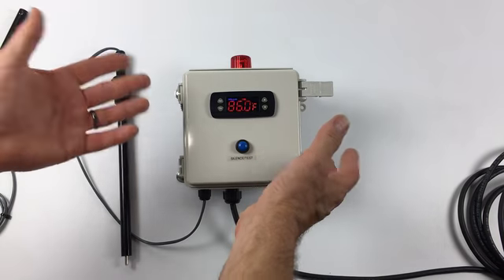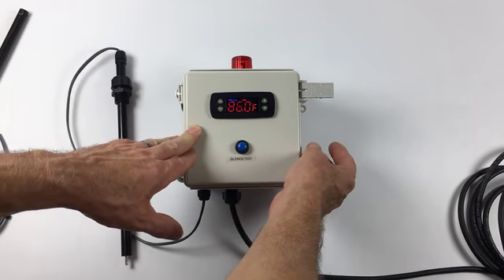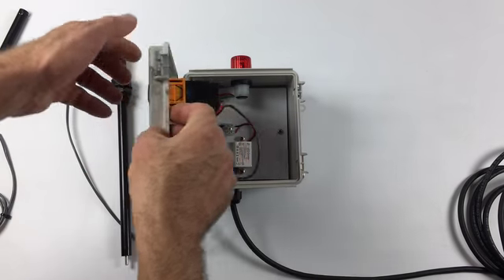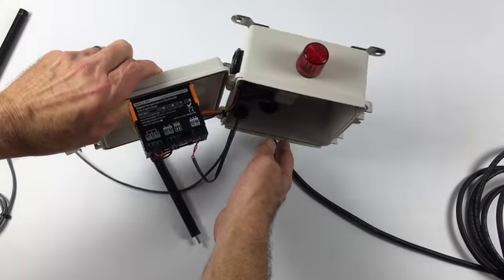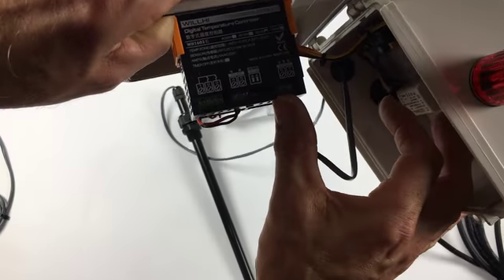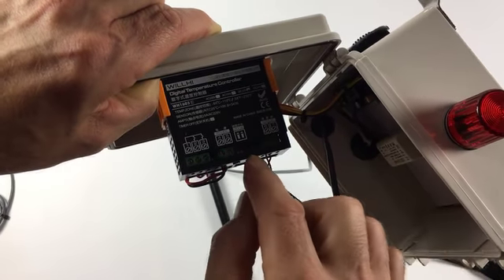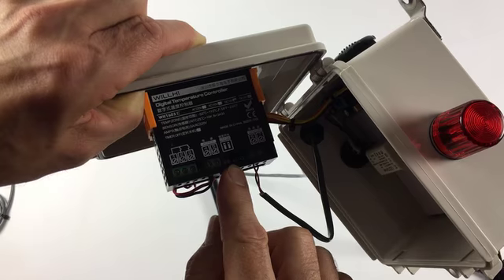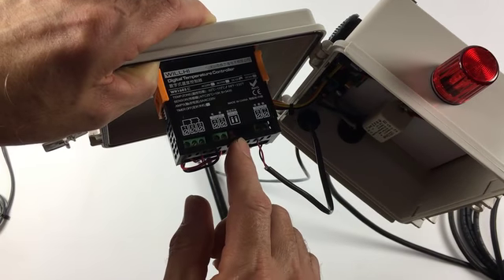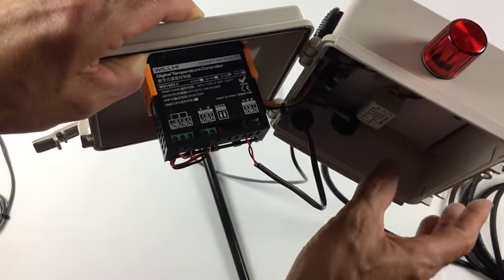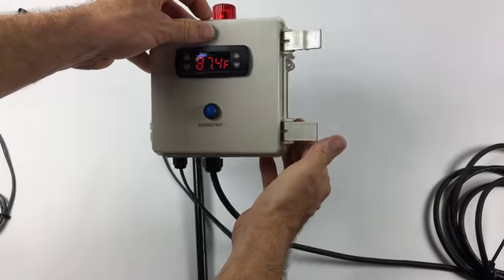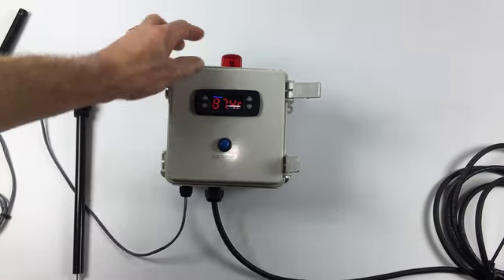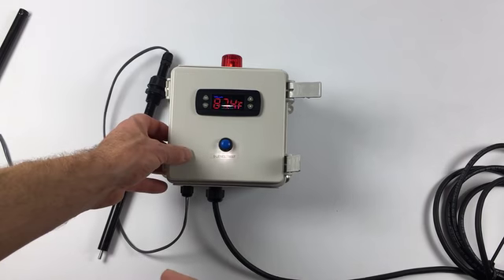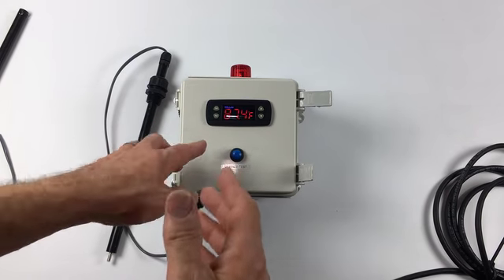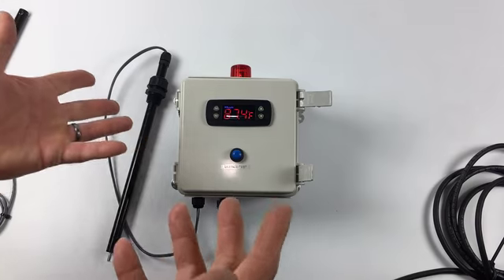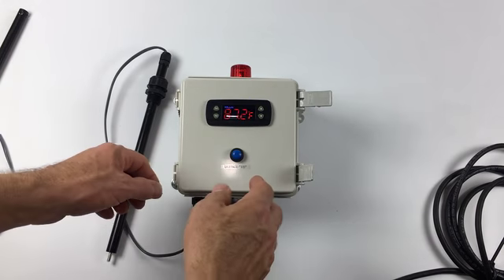And you might think, well, an operator can just change that to get around it. But there's a lockout function right here. There's 2 dip switches there. Hopefully you can make them out. If either one of those is slid to the on position, then the operator cannot change that maximum temperature. So basically, by setting this you can lock the operator out so that the set point can never be changed if that's appropriate for the application.